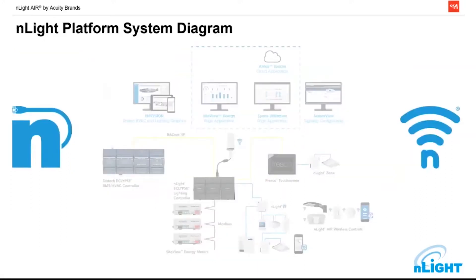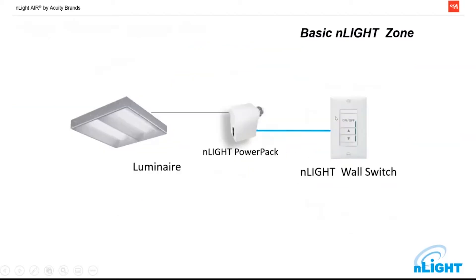Here's a basic overview of the entire system — we're going to deep dive into one or two parts of it. A very basic nLight zone consists of a switch, a power pack, and a light fixture. We're going to run Cat5 from our switch to our power pack, and then wire out from our power pack to the luminaire itself. Very basic, and we can scale.